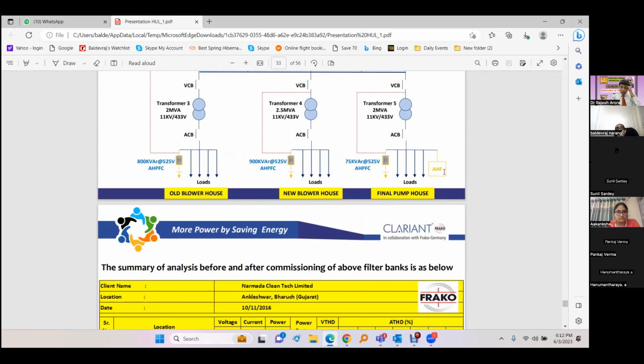But what happens in the industry, we have seen there is a lot of, you can say, marketing gimmick going on. What they do is they say you improve the power factor with passive and use active for the harmonic filtration, two systems. So if we go that way, suppose we have solved the problem with 100 amperes, the active filter will need maybe 1000 amperes. And it's a costly item. So if we customize this passive filter and remove whatever is possible with passive, this requirement can come down. So that is what we try to do.